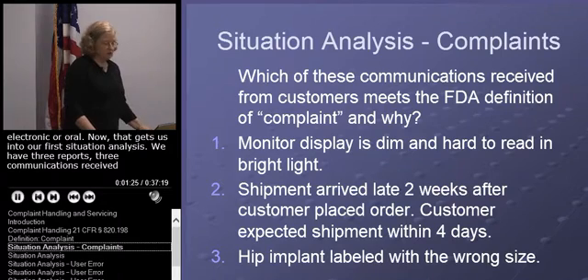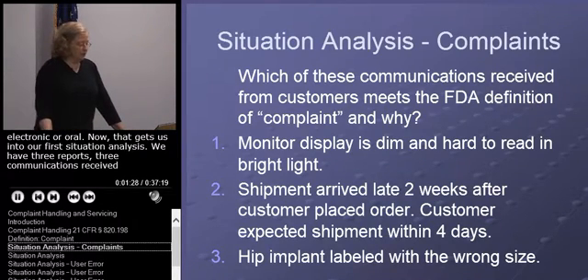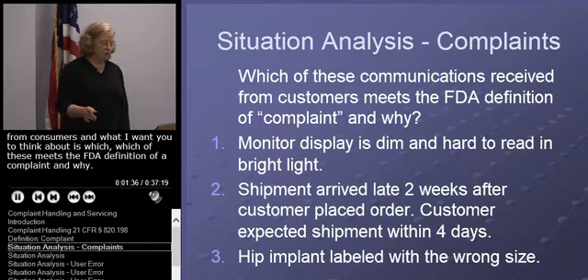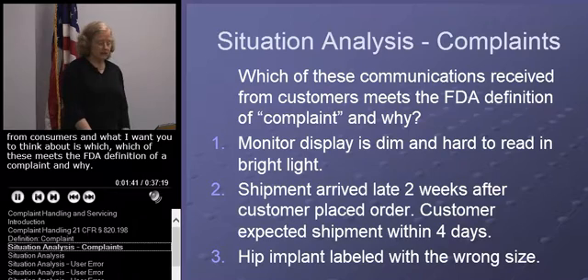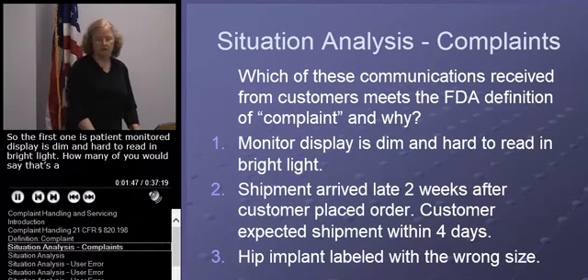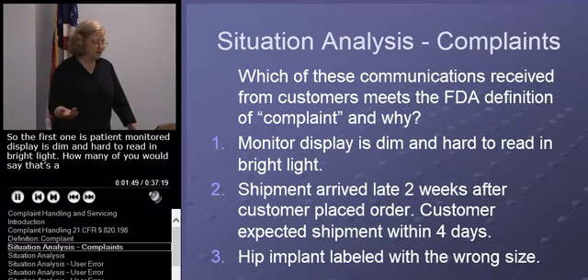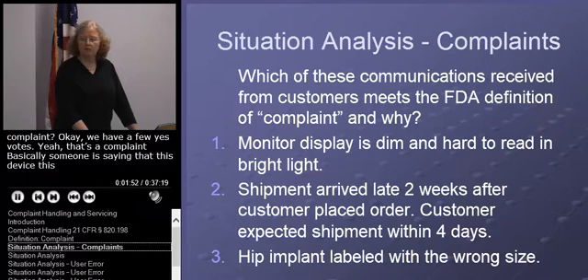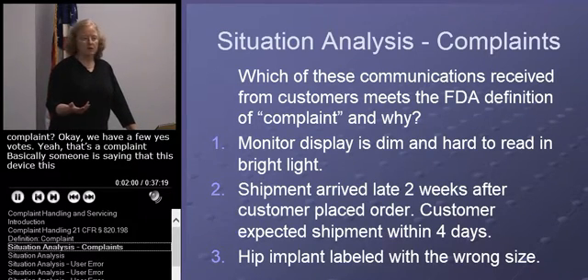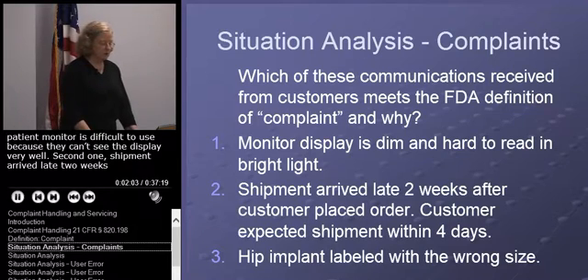Now that gets us into our first situation analysis. We have three communications received from consumers, and what I want you to think about is which of these meets the FDA definition of a complaint and why. The first one is: patient monitor display is dim and hard to read in bright light. That is a complaint — someone is saying that this patient monitor is difficult to use because they can't see the display very well.